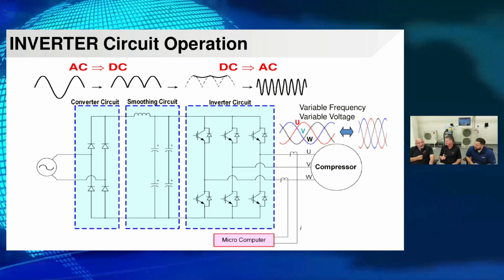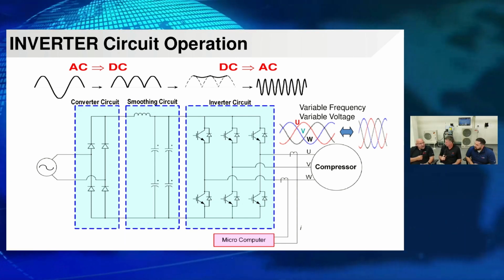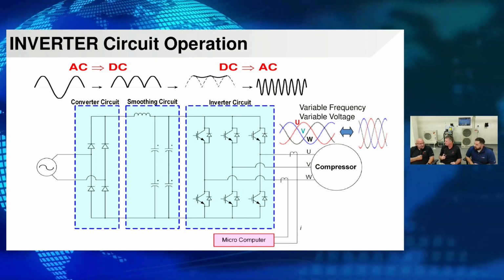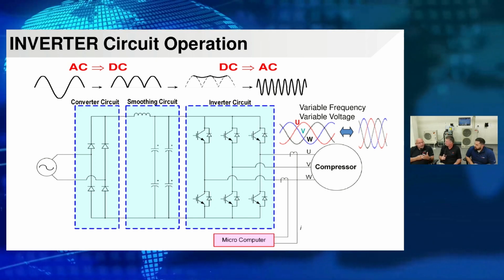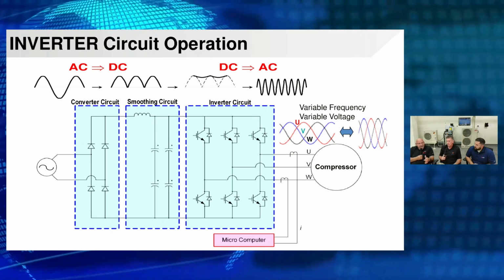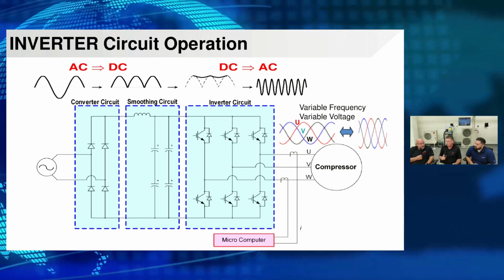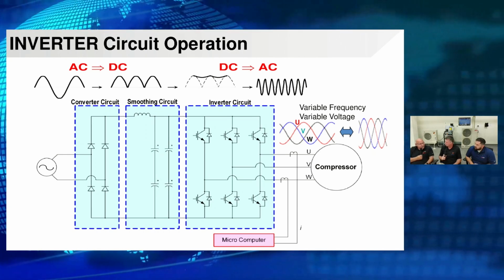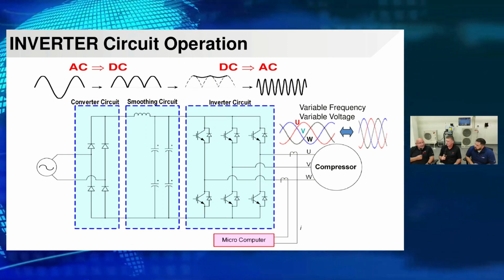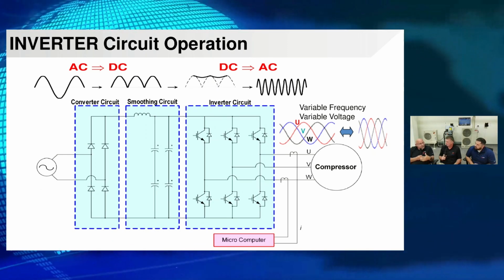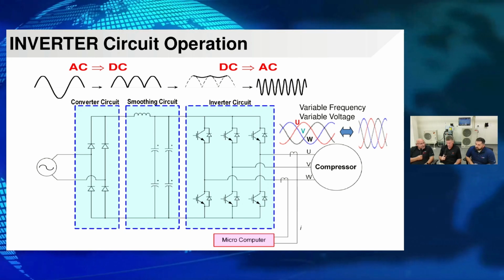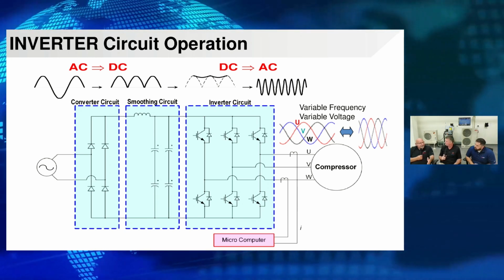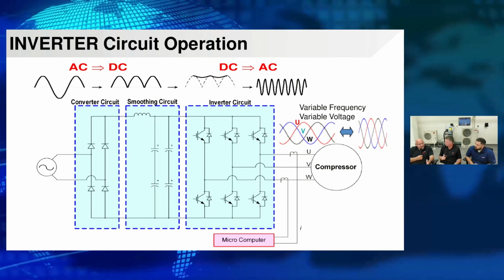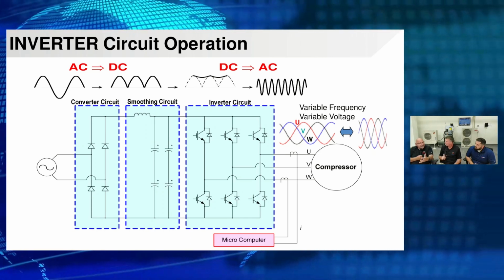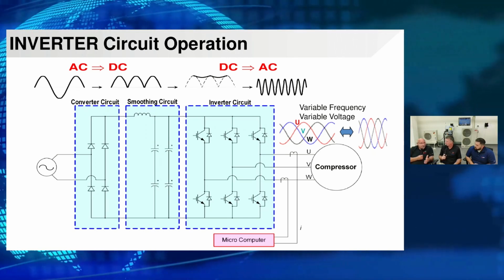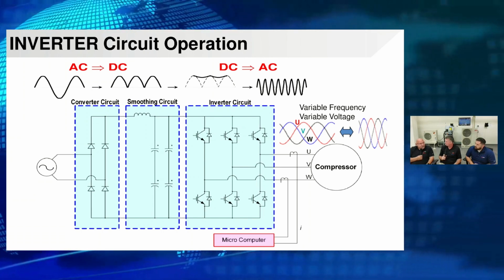Yeah. So what is the frequency coming into the outdoor unit? Well, in the United States, 60-ish hertz. 60 hertz if it's clean. Yeah, exactly. That's why I say ish. Okay. So now, once we come out of the inverter, we can manipulate that frequency. Right. So if we want to slow down the speed of the compressor, we can lessen the frequency going to the compressor. If we want to speed it up, we compress that signal so that the compressor ramps up in speed. So it's constantly looking at demand, and the inverter is what is sending that voltage, because it is AC voltage when we look for it, right, to the compressor or the motor.